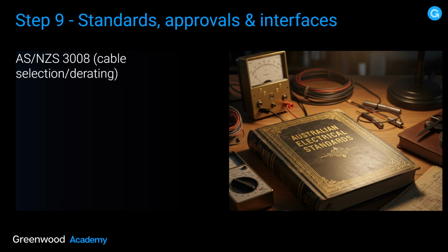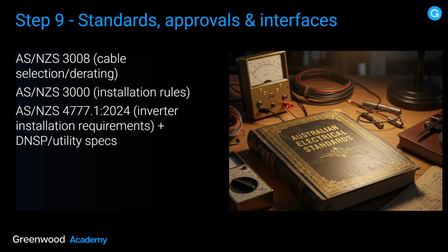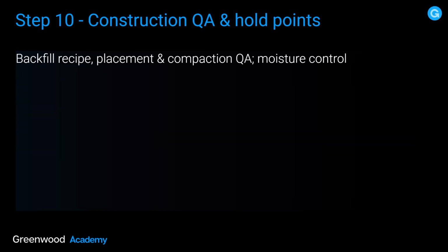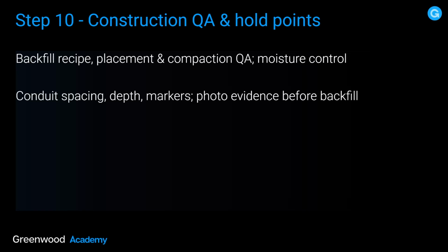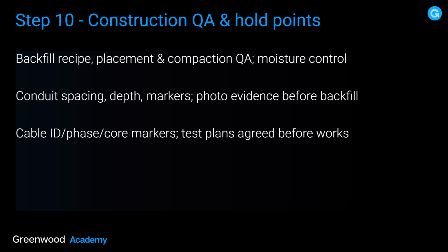Step 9, standards, approvals, and interfaces. So the Australian standards AS/NZS 3008, cable selection and derating. We're looking also at AS/NZS 3000, that's the installation rules. Also take a look at AS/NZS 4777.1 2024, inverter installation requirements and DNSP utility specs. Step 10, construction, QA and hold points. Backfill recipe, placement and compaction QA, moisture control. Conduit spacing, depth, markers, photo evidence before backfill. Cable ID, per phase, core markers, test plans agreed before works.